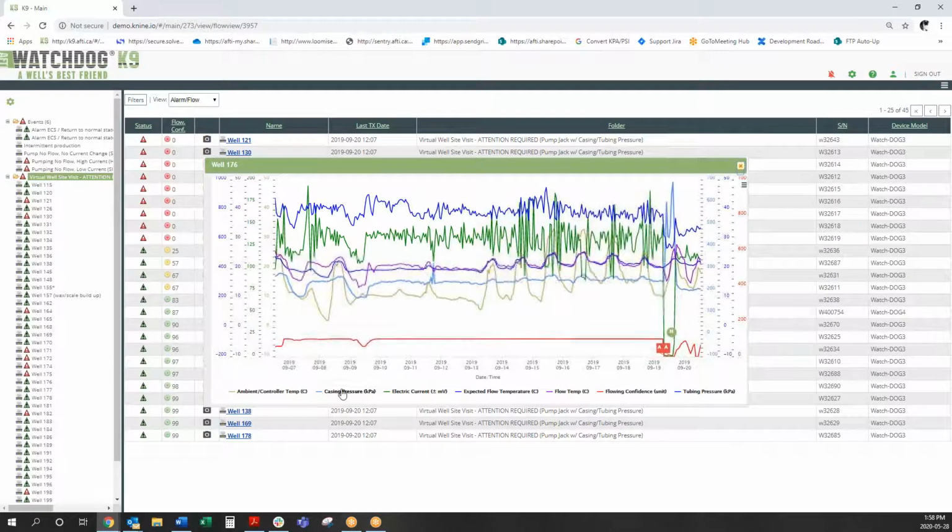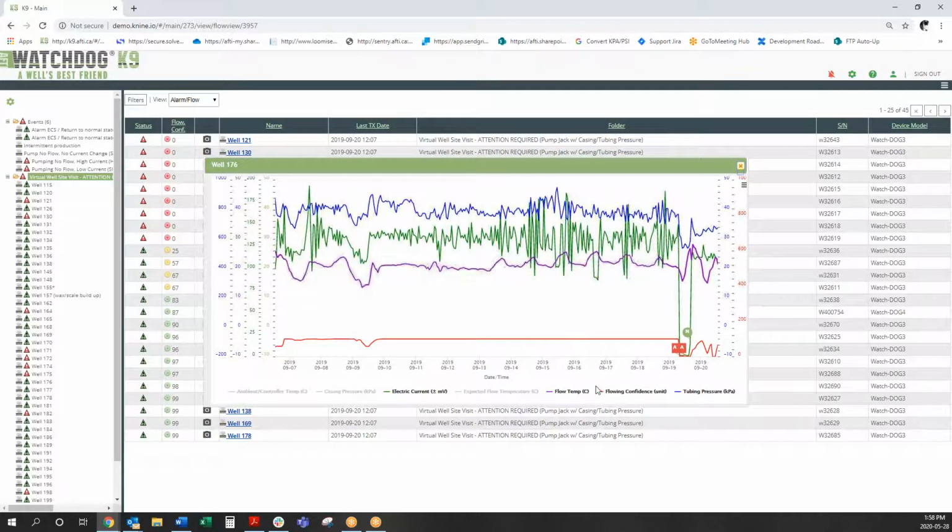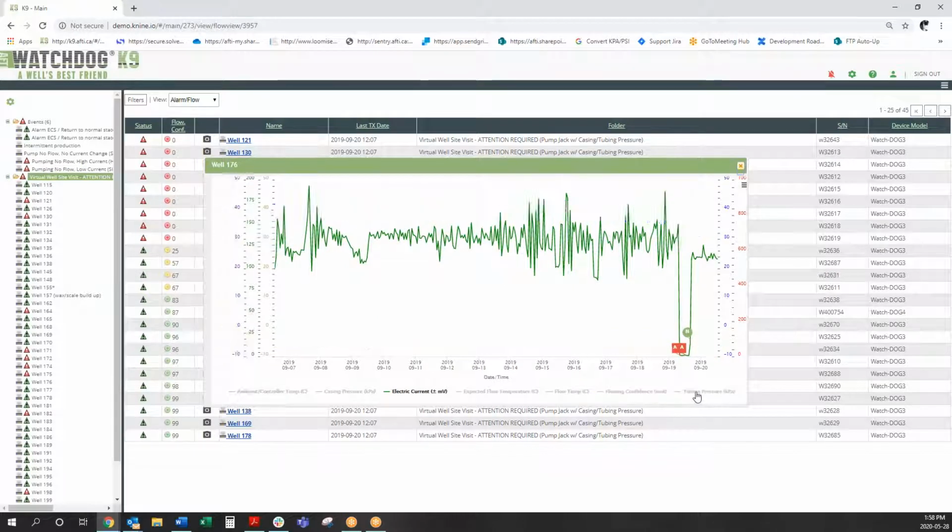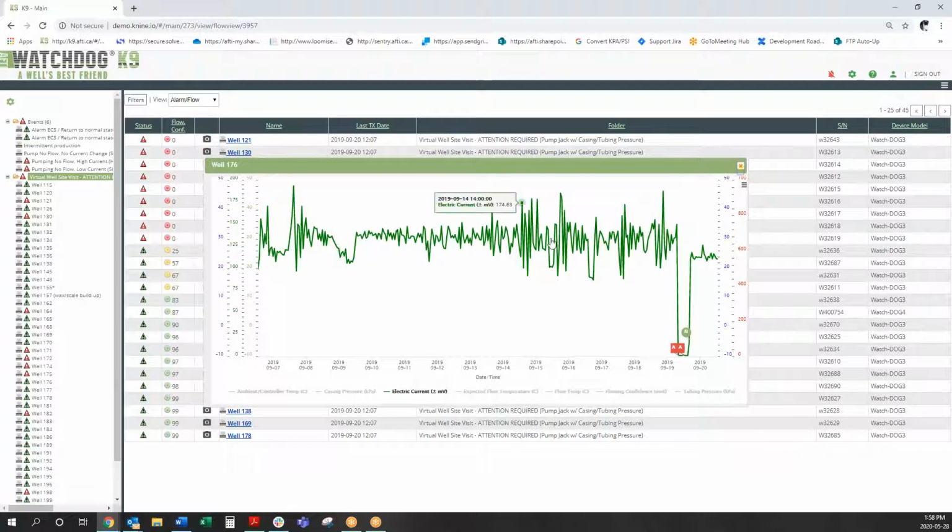Okay, interesting. So there's a different pattern here. It looks like the pump is working pretty hard. And then here is interesting. Let's see what temperature is doing in relation to it. The reason I'm curious about this is because this is normally well above 120, but here it's below 120 and trending.